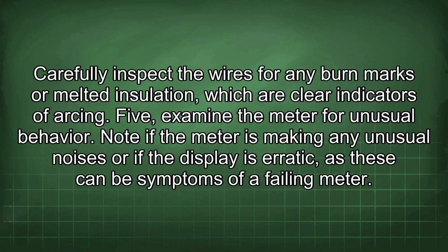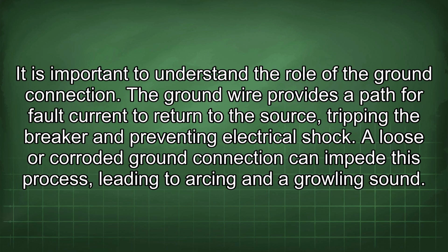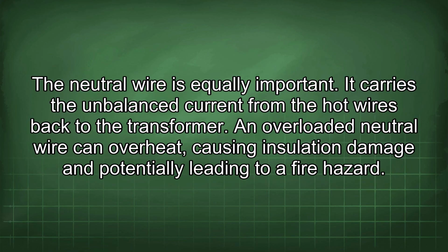of a failing meter. It is important to understand the role of the ground connection. The ground wire provides a path for fault current to return to the source, tripping the breaker and preventing electrical shock. A loose or corroded ground connection can impede this process, leading to arcing and a growling sound. The neutral wire is equally important. It carries the unbalanced current from the hot wires back to the transformer. An overloaded neutral wire can overheat, causing insulation damage and potentially leading to a fire hazard.